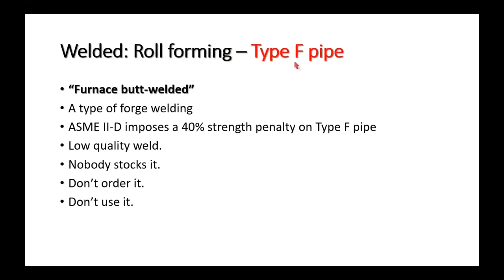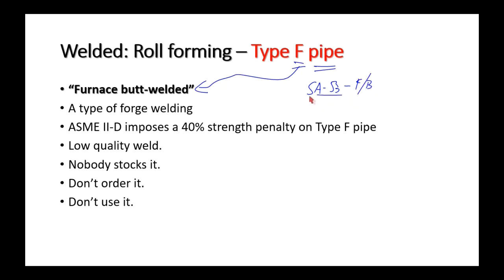Type F pipe — the F stands for furnace butt welded. For example, SA-53 Grade F/B: A53 is the ASTM designation, S is for ASME, B is the grade of material, and F stands for Type F pipe, which is furnace butt welded. This is essentially forge welding — what a blacksmith did with a hammer and forge — and it makes a weak weld.